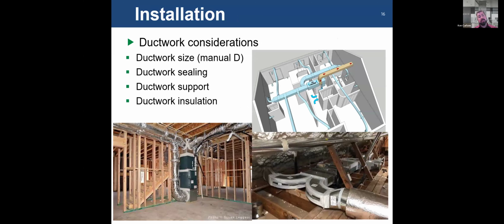So, ductwork considerations. You've done your ductwork sizing per Manual D. All right, you got all your sizes. You got your layout. You install your ductwork. I can't stress enough ductwork sealing. All right, and when I mean sealing, I mean sealing up joints. Most ductwork, particularly in residential applications, is slip and drive. It's a real loose connection, or you're cutting in around ducts for flex or branches. Depending on which type of collar you're using, it could seal well, and it could be a real loose connection that allows a lot of air to escape.